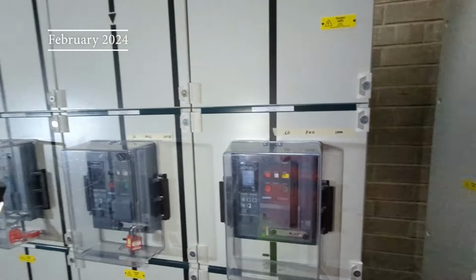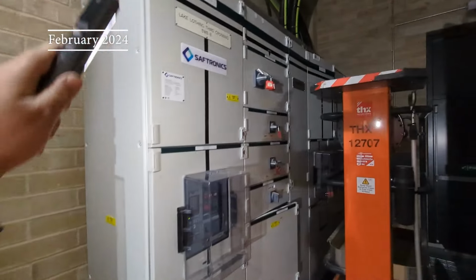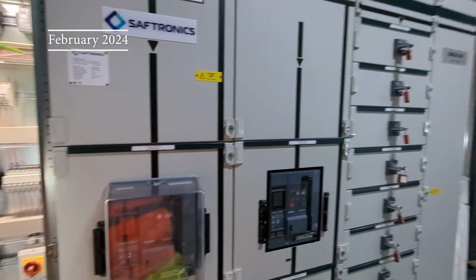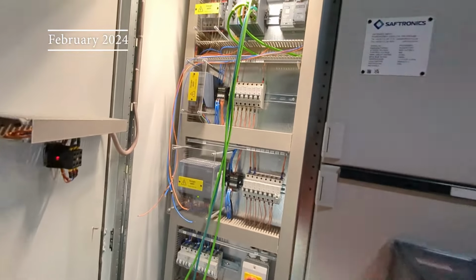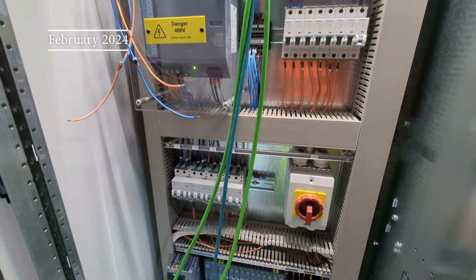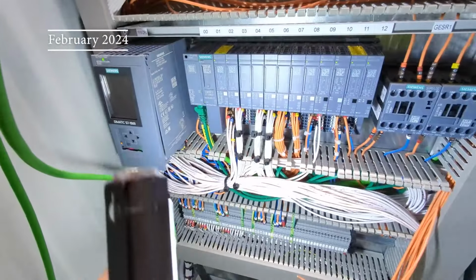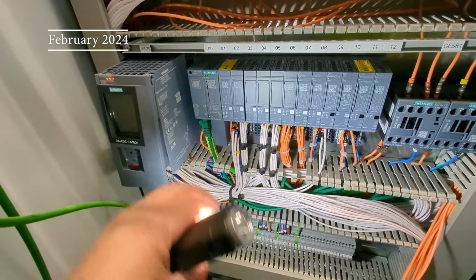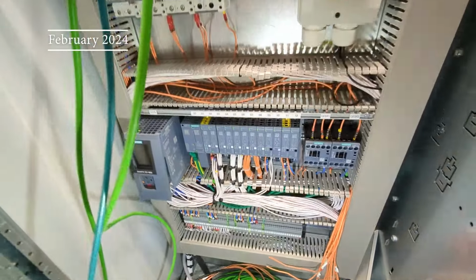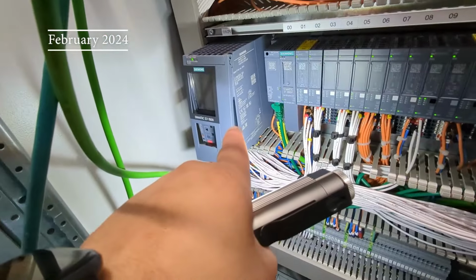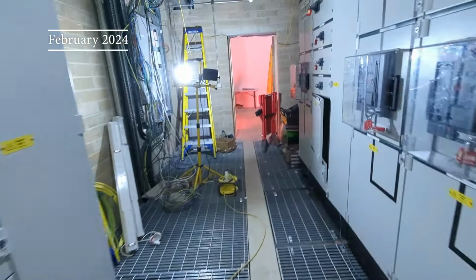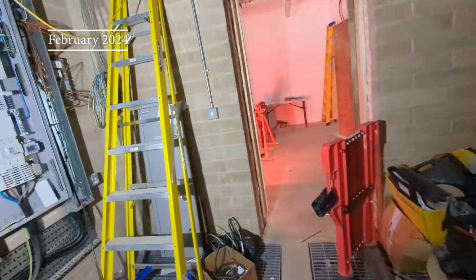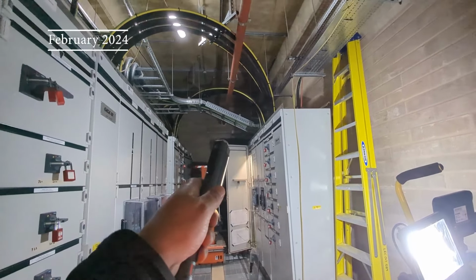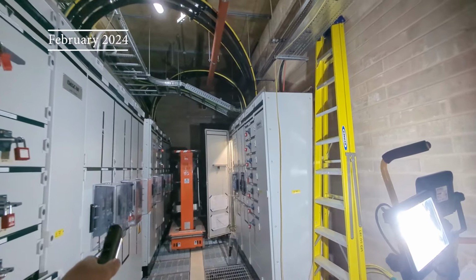So what you've got is 2 switchboards, switchboard A, switchboard B. One of them powers this panel, which is like the PLC panel. So this is where you've got all of your network switches, blah blah blah. And then here's the PLC rack, 1500 PLC with ET200 SP remote I/O. So that controls this tiny thing, lifts the whole entire bridge. So if I come out of here, that's the switchboard room.